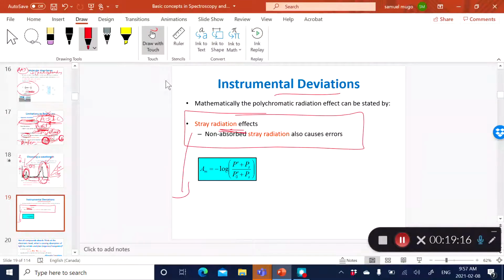And so the lighting in the room is going to impact, of course, the analytical radiation of transmittance and the incident beam, and you can see that it's going to affect your absorbance that is generated. So stray radiation, either coming from the lighting in the room, or also due to the scattering from the dust particles that are present on the cuvette, could be another impact to the sensitivity of your absorption spectroscopy.